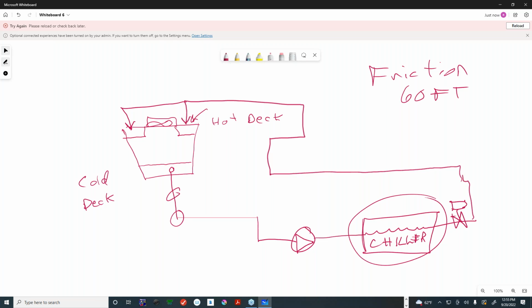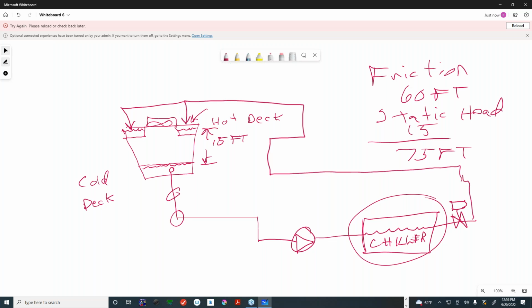In order for the pump to overcome the height of the cooling tower, I have to take the water level in the hot deck and the water level in the cold deck, and let's assume that vertical distance is 15 feet. I have to add that, which is sometimes referred to as my static head. In my case 15 feet, so 60 plus 15 is 75 feet. So whenever I have an open system, I have to do not only the pressure drop calculation as a function of the pipe, but also consider the static head, or the height that I have to raise the water to accommodate this tank configuration.